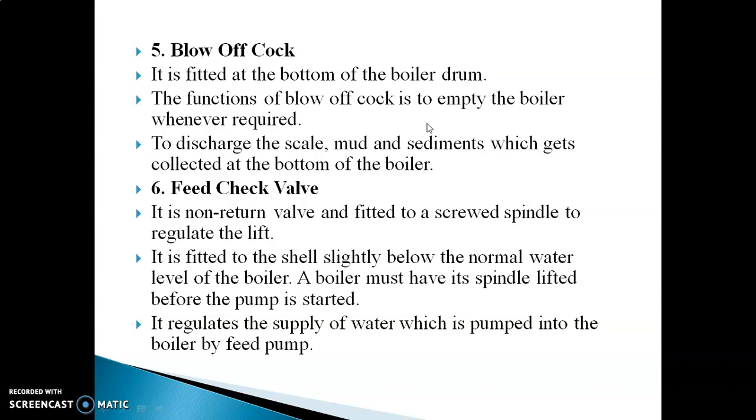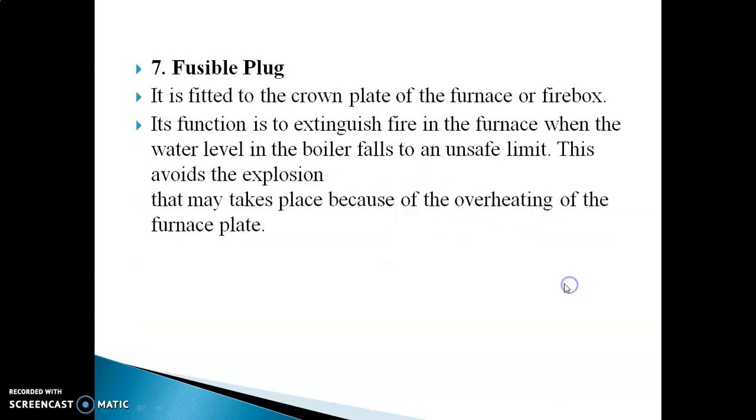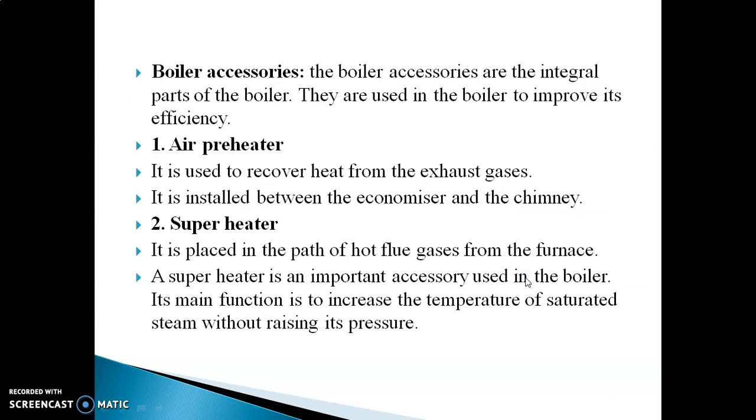Feed check valve. It controls the supply of water to the boiler when the feed pump pressure is less than boiler pressure or the pump is stopped. Fusible plug. It is fitted to the crown plate of the furnace or firebox. The function is to extinguish the fire in the furnace when the water level of the boiler falls to an unsafe condition. Boiler accessories.